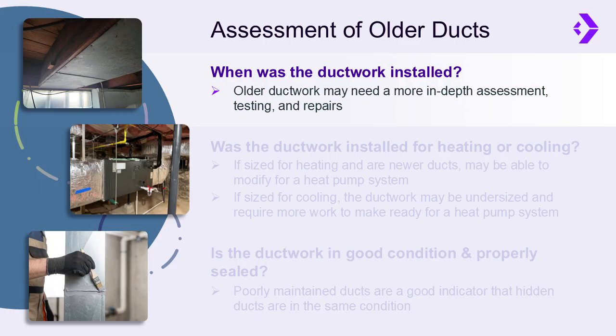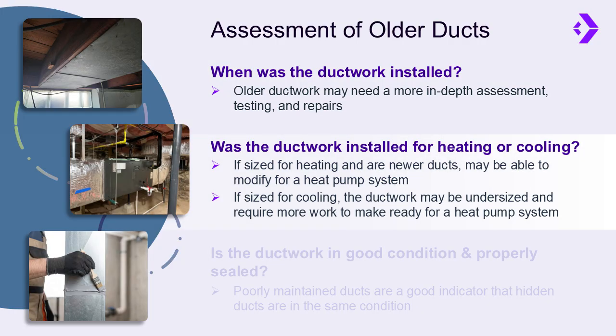The age of ductwork will help to reveal potentials for leaks, reduced efficiency, impacts to indoor air quality if a more in-depth assessment needs to be performed, and possible buildup of dust and dirt. Next, consider whether the ductwork was originally sized for heating or cooling. If it was sized for heating and is relatively new, it might be possible to reuse with some modifications for a heat pump system. If it was sized for cooling, it could be undersized and may require additional work to meet the demand of a heat pump.